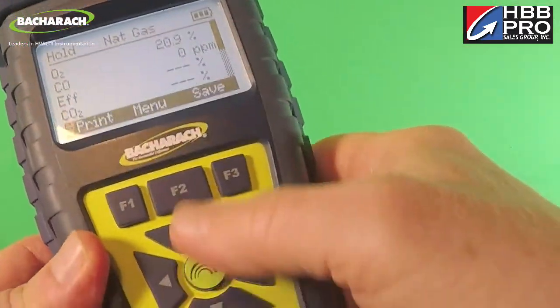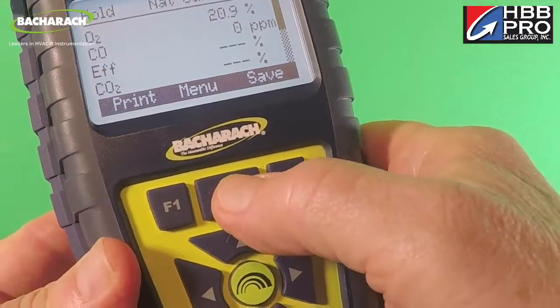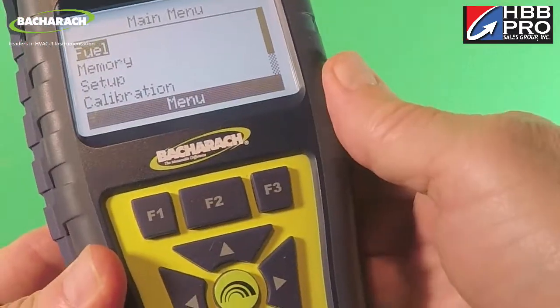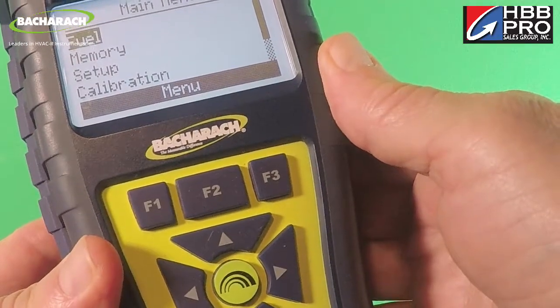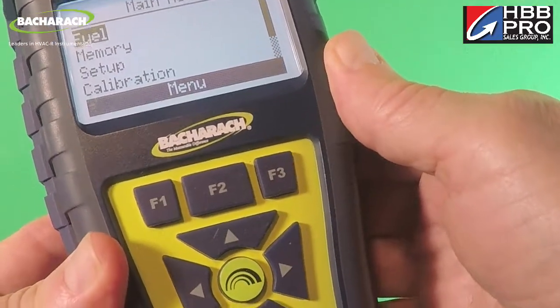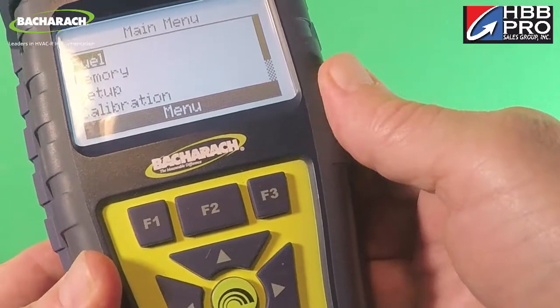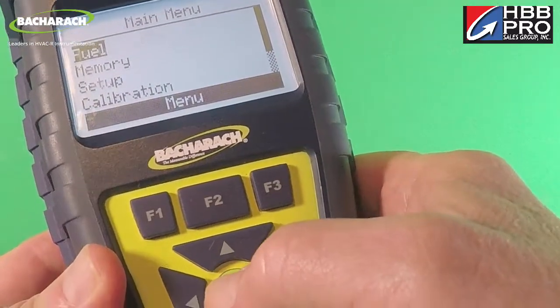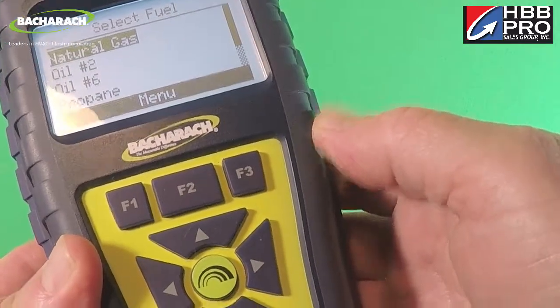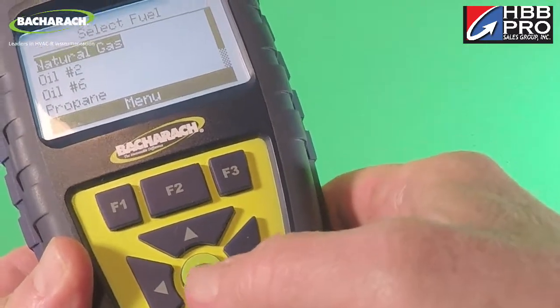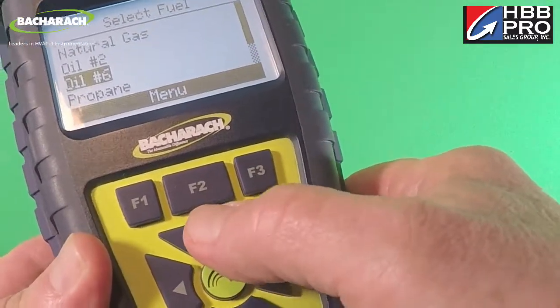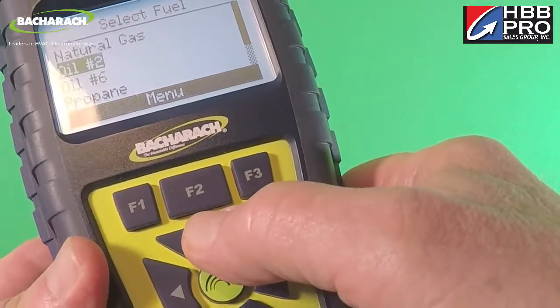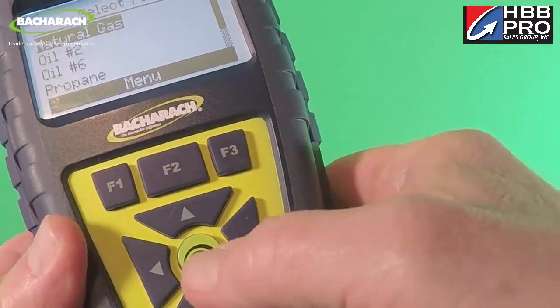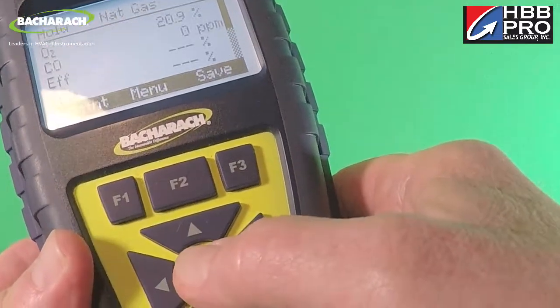So let's go to the main menu, which is the F2 button. We'll press that. And just to save some time, I'm only going to address the settings you really need to be concerned with. To ensure that the calculated readings are accurate, you need to enter in the right fuel types. Let's say we've got natural gas. You can see we have propane. I don't know if I'd run number 6 through one of these, but oil, natural gas, whatever. Just hit the enter button.